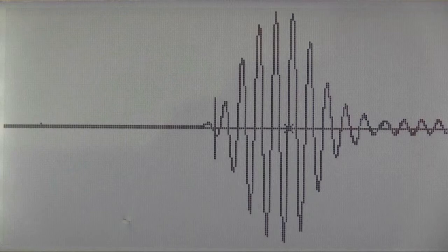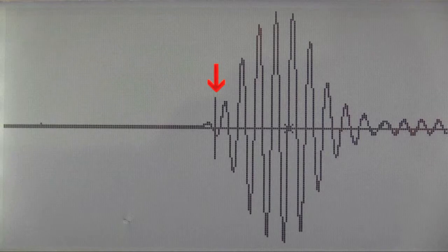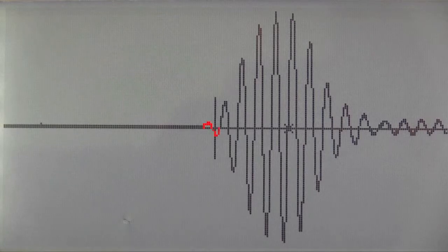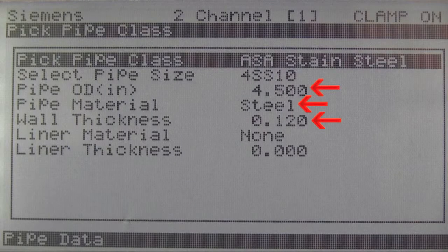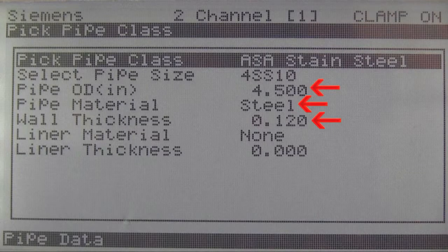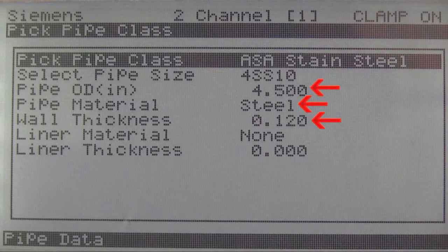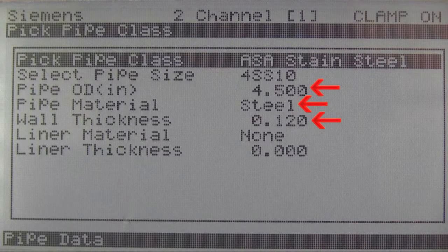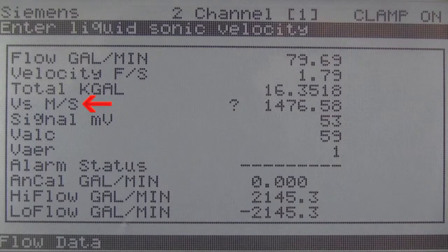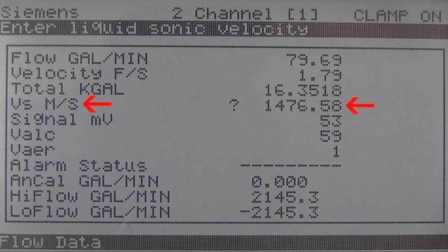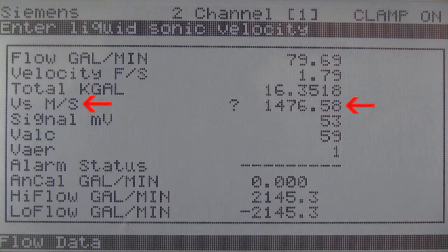If you look at the left side of the wave, you will see a vertical bar which marks the measured point of arrival of the signal. Identifying the position of this bar in the first wave cycle of the signal confirms the correct measurement of transit time. Couple this with ensuring the accuracy of the dimensional programming, and you are assured of a correct sonic velocity measurement. Now you have also established the sonic velocity of your product, which enables immediate verification on future installations.